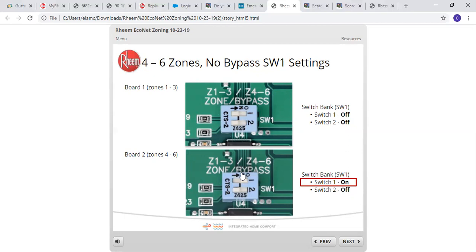Now there again, bear in mind, if you're going to make these changes on dip switches, it has to be turned off when you change it, and then turned back on. So the board will accept the dip switch change. If you change it on the fly when it's powered up, the board will not accept the dip switch change. And if it doesn't accept the dip switch change, you will get some erratic operation.